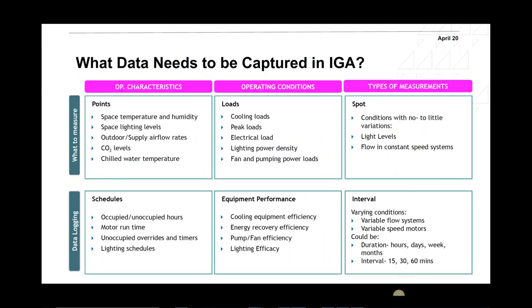What kind of data needs to be captured in an IGA? That's not comprehensive, but I tried to put some of the data that is normally required. Operation characteristics, what to measure: points like space temperature, humidity, space lighting levels. Again, you need to make sure that whatever ECMs or EMs we're proposing, we're not affecting the standards of comfort, we're not affecting the indoor environmental quality, that is temperature, humidity, indoor air quality, visual light, and sound. So you need not affect negatively any of these aspects. You should improve them basically, or keep them the same. Normally, you should aim to improve them. So you need to take the space temperature and humidity to make sure that there is proper thermal comfort.